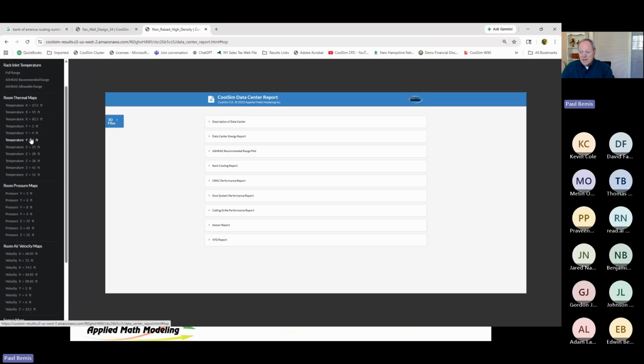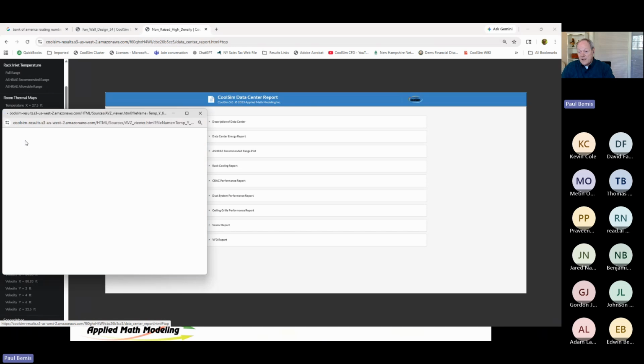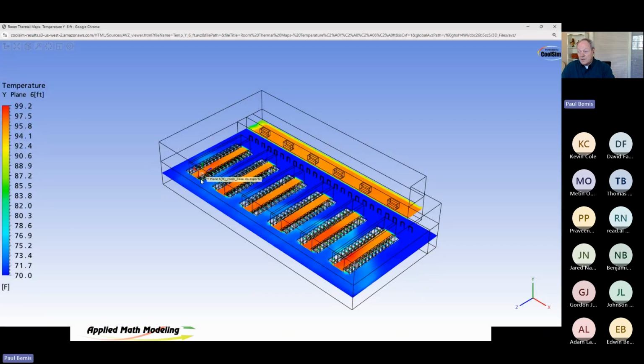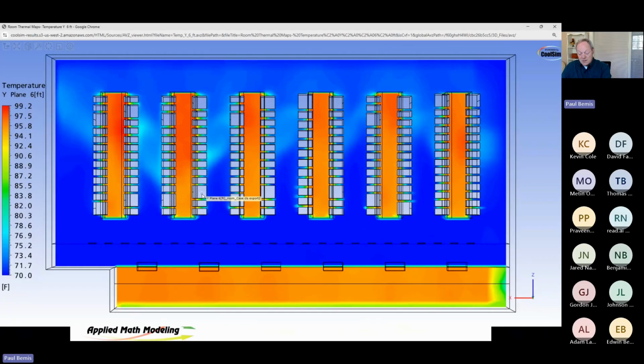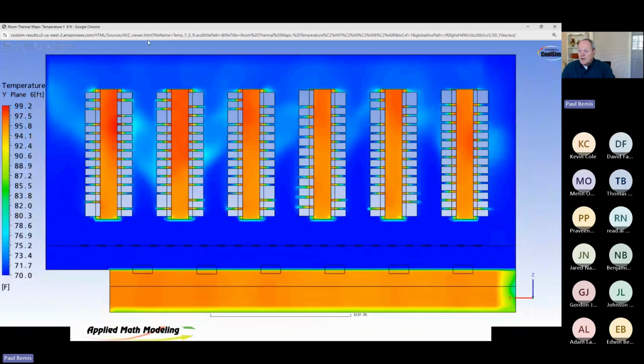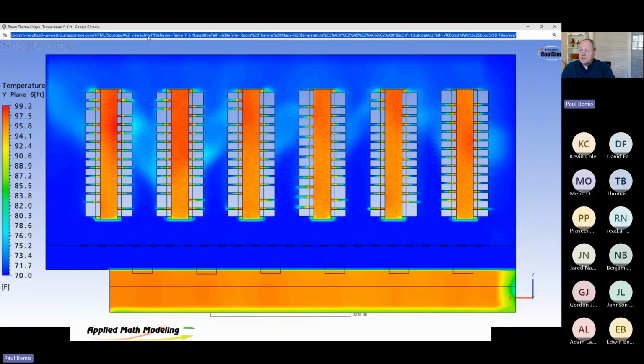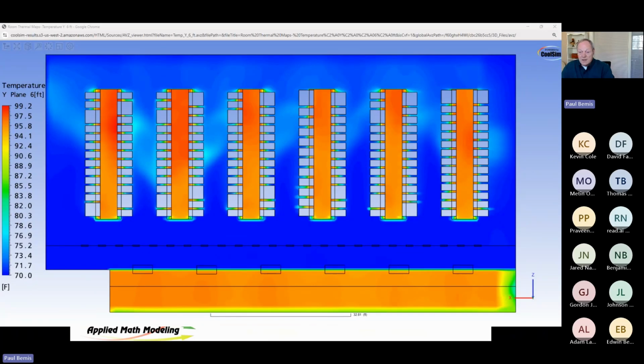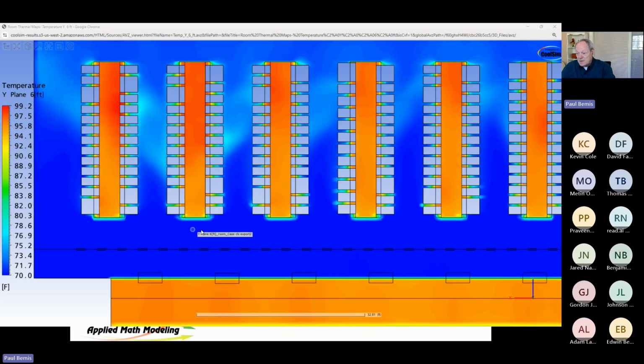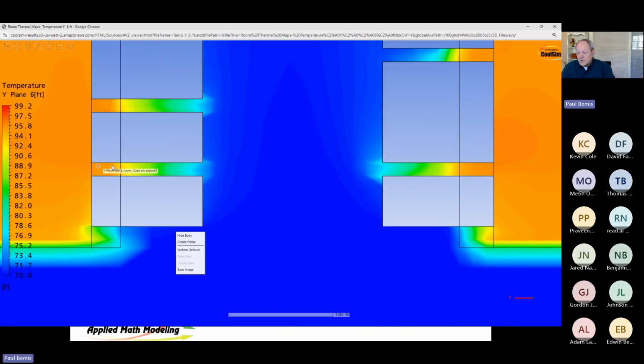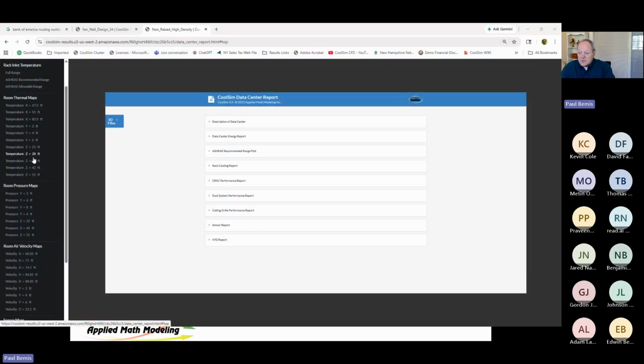So let's take a slice at 6 feet. We'll go up high on the rack and take a look. And let me, again, hit the Y key and normalize it with N. Take perspective off. I can, again, share this with you if you want. So let me copy this and put it in with Control V. So it's in the chat if you want to see it. And you see it's leaking, and again, high velocity on this end. Look at the leakage right there. It's coming right out into the cold aisle because the pressure differential here is not in the right direction. It's actually inverted. And I think maybe in this one, the pressure is scaled a little bit better, so you're able to see it.